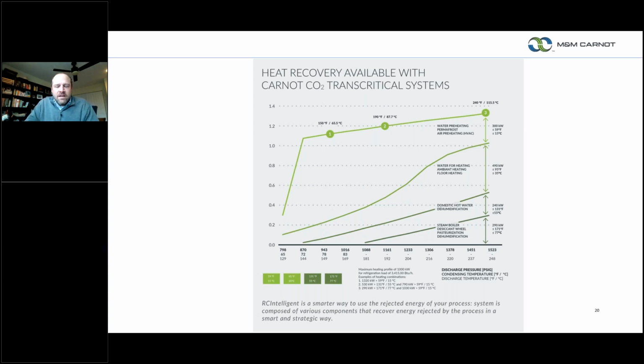But that 131 degrees Fahrenheit hot water is one of our sweet spots. So basically, I have a 280 kW chiller, or 80-ton chiller, that's making 300 kW worth of heat, excuse me. As you increase the temperature with a CO2 based system, the amount of heat capacity that you can get out of that machine or system will decrease. So if you're going up to 140 degree water or 150 degree water and your chiller's 280 kW, you're going to get less than 280 kW worth of heat as you start increasing those temperatures. On the industrial refrigeration side of our business, those systems are almost always very custom for every application, and every degree and every kW is designed for what that application is.